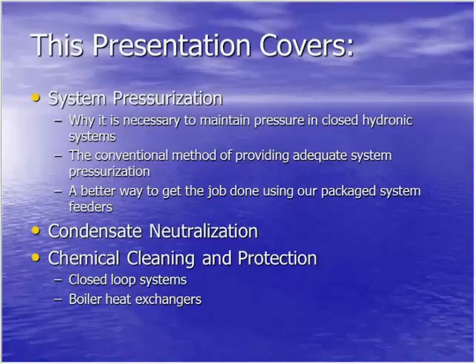mainly system pressurization units. I'll talk about why it's necessary to maintain pressure in closed hydronic systems, explain the conventional method of providing adequate system pressurization, and then introduce to you or elaborate on a better way to get the job done using one of our package system feeders. Also talk briefly near the end about condensate neutralization and chemical cleaning and protection for closed loop hydronic systems.